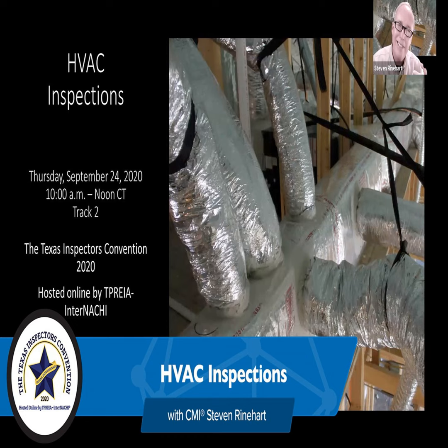Can't take them from outside the house. Can't have your mechanical system heating and cooling the garage. So any place that parks cars cannot be heated, cooled, or returned with the same unit that does the house. It can have its own.